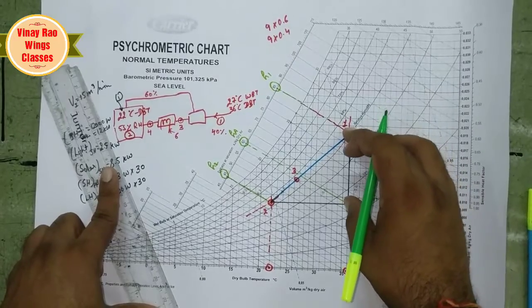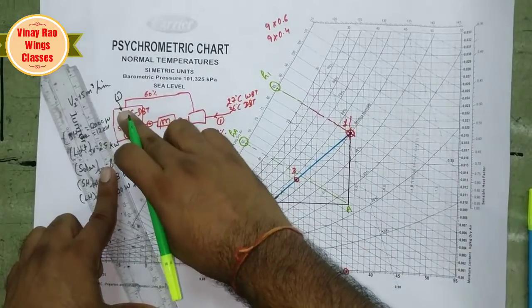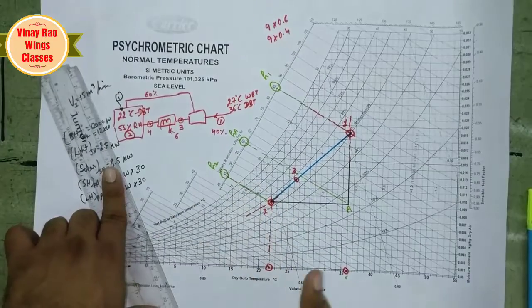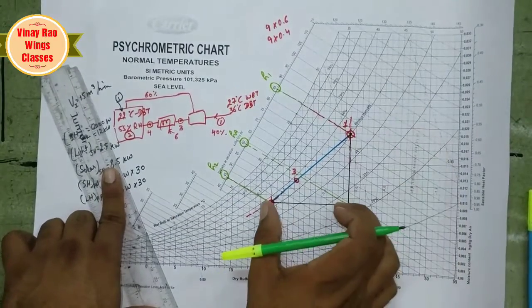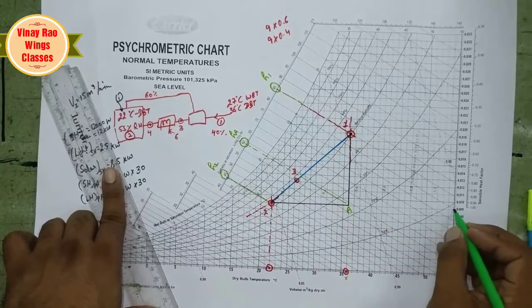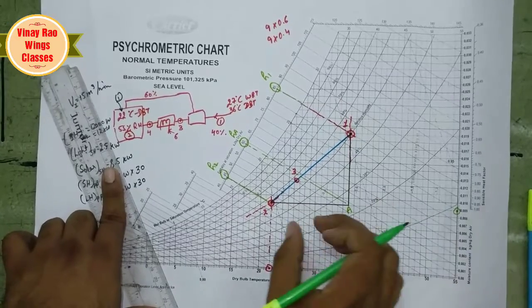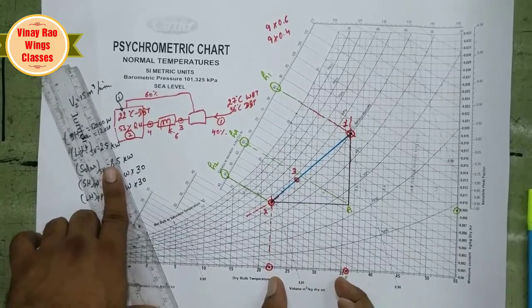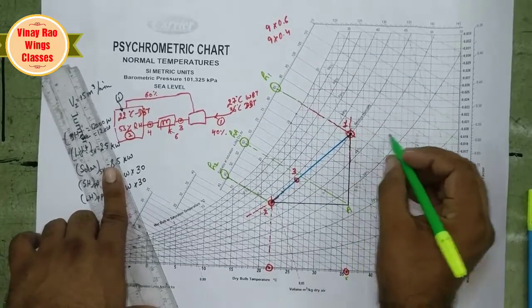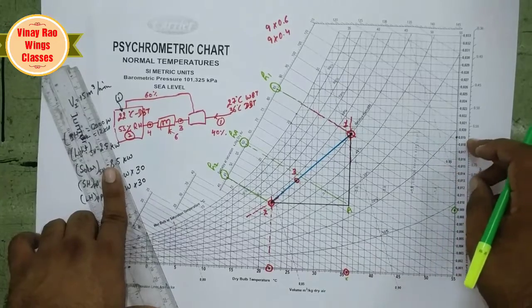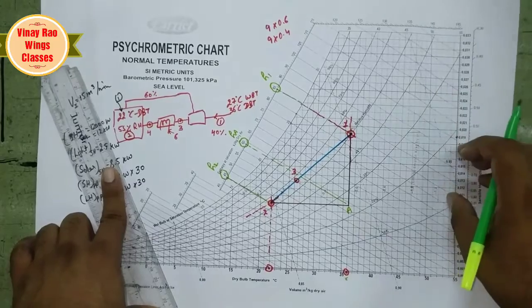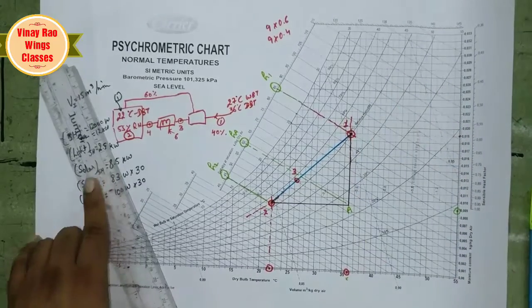It is latent heat due to infiltrated air, outside air directly mixing into the room. The outside air has some latent heat and some sensible heat. This is the part of latent heat, because without change in temperature, there is change in moisture content from 22 to 36. In this case, there is change in humidity from 0.019 to 0.009. There is change in humidity due to outside air.